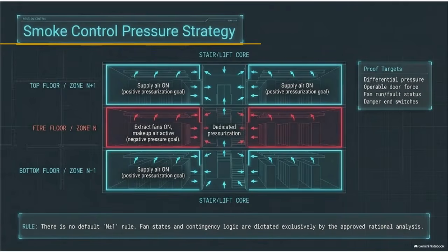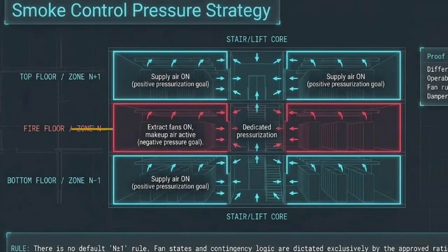This building cross-section shows the active smoke control pressure strategy. The matrix turns on extraction fans to create a negative pressure goal on the red fire floor, while commanding supply air to positively pressurize the blue adjacent zones, containing the smoke.